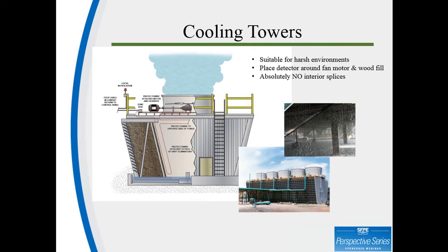Cooling towers are basically a swamp and are another popular application for digital linear heat detection. The high-risk items within a cooling tower are the fan motor and gearbox. There are limited detection technologies or even products that can survive within an operational cooling tower. Optional, but highly recommended, is the additional coverage placed in and around the wood fill. While the tower is operational, the wood is soaked and should not ignite. But if the tower is taken offline for maintenance or some other reason, the wood fill dries out and is highly combustible.